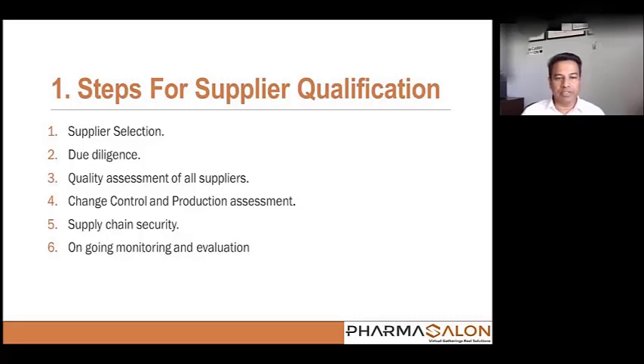Change control and production assessment. If there's any change in the supplier's supply chain, if they change their suppliers, or if the product they are supplying has any changes, there's proper documentation into change control and proper communication to us. Once we get that communication, we do another qualification or abbreviated way of making sure that particular product meets the necessary requirements.